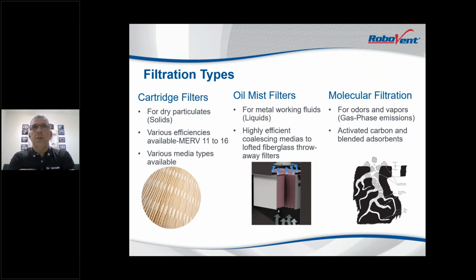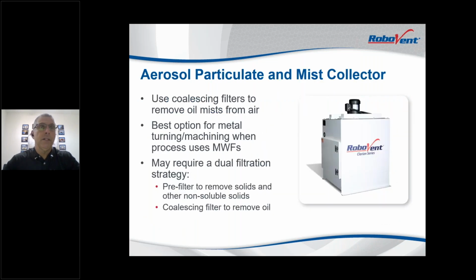If you're dealing with odors, that is constituents in the gas phase, a filter will not capture those odors. So you'll need to use what we call molecular filtration. It's basically activated carbon, activated charcoal that is able to absorb those gas phase emissions and get rid of the odor from the process. So that's always a possibility.